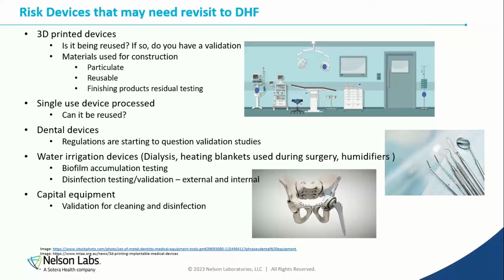Dental devices, like we talked earlier, regulations are starting to question validation studies. They don't have validation studies, but they're using these devices that are going in our mouth, and they're getting hit very hard. And they're just learning what an IFU is. If you go to your dentist, there is one process only: rinse, sonication, sterilize. Same program, same everything. Now, are they validated to that, all those instruments? Probably not, but these processes are definitely being audited and looked at.